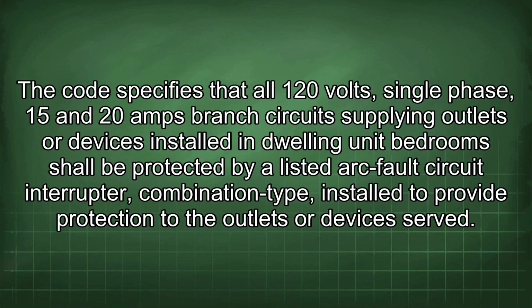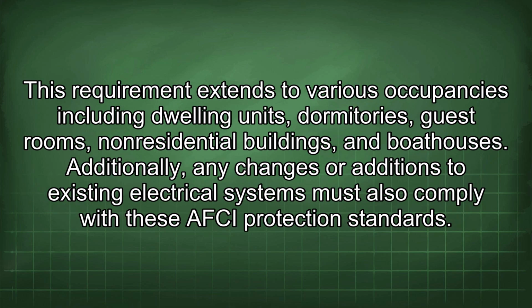The code specifies that all 120 volt, single phase, 15 and 20 amp branch circuits supplying outlets or devices installed in dwelling unit bedrooms shall be protected by a listed arc fault circuit interrupter combination type, installed to provide protection to the outlets or devices served. This requirement extends to various occupancies including dwelling units, dormitories, guest rooms, non-residential buildings, and boathouses. Additionally, any changes or additions to existing electrical systems must also comply with these AFCI protection standards.